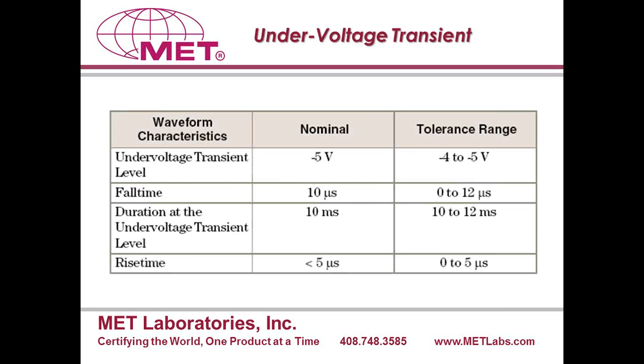At this point, I want to jump into the main topic of this discussion, which is the undervoltage and the overvoltage. Before I go there, I just want to mention that in addition to the undervoltage and overvoltage requirements, there is a third requirement, which is the impulse transient requirement. I purposely did not include that in this presentation because that has been a very well established test method for several years. There are some minor challenges when it comes to testing the higher currents.